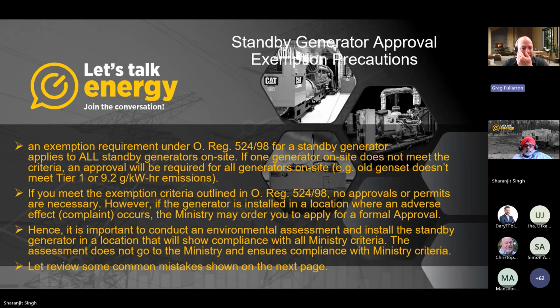So an exemption requirement under Reg 524 for a standby generator applies to all standby generators on site. And I mentioned this already. If one generator on site does not meet the criteria, an approval will be required for all generators on site. For example, an old genset doesn't meet tier 1 or 9.2 gram per kilowatt hour emissions. If you meet the exemption criteria outlined in O. Reg. 524/98, no approvals or permits are necessary. However, if the generator is installed in a location where an adverse effect complaint occurs, the ministry may order you to apply for a formal approval. And I've already responded to a few of these, and they're very difficult because the equipment's already installed, and now we have to do some pretty cost-intensive things to get them in compliance.